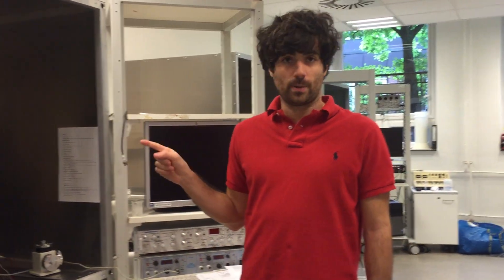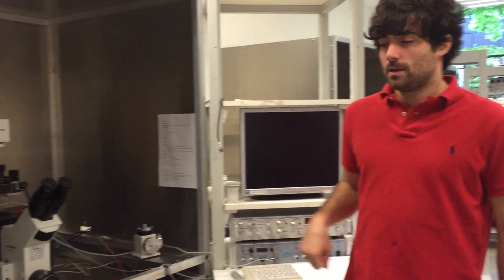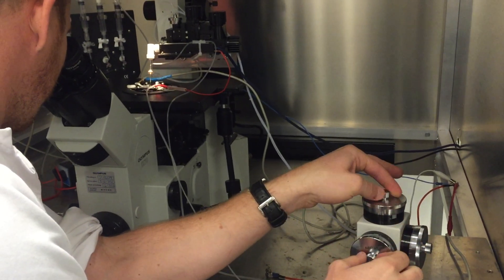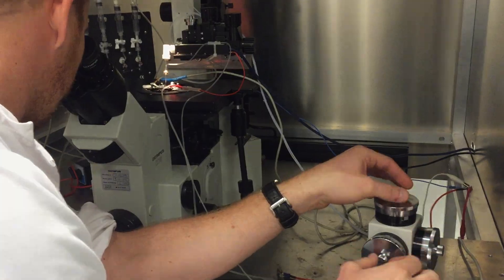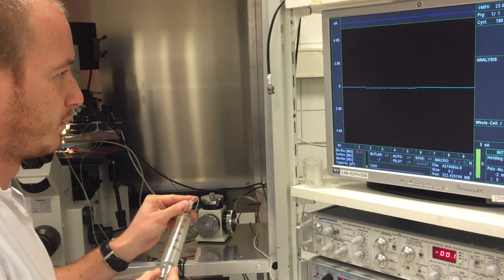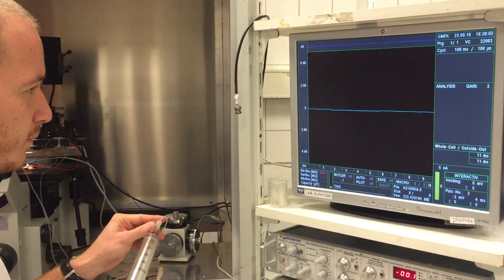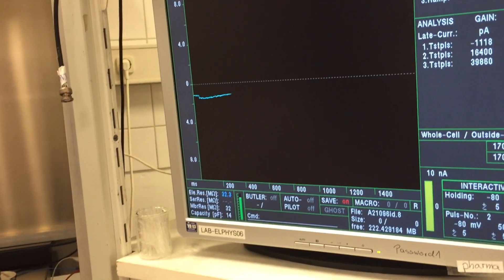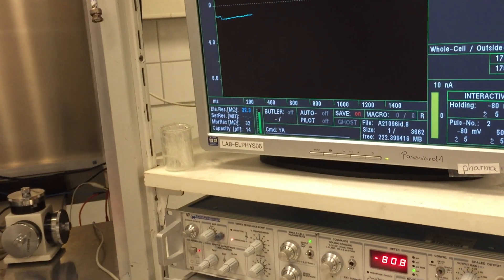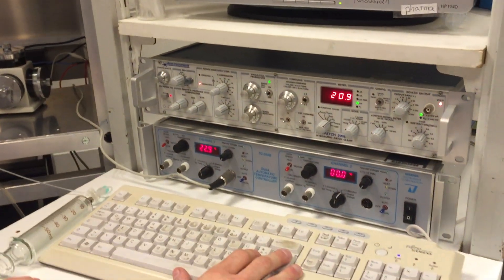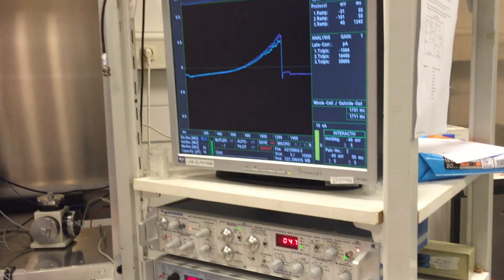First I am going to show you the patch clamp. It is an instrument called this way because you can patch the membrane of the cells. At the same time you can clamp the voltage at the value that you prefer. You go close with an electrode to the membrane of the cell, get the seal, then reach the membrane by applying pressure, in order to have access to the cell and measure the ion currents.